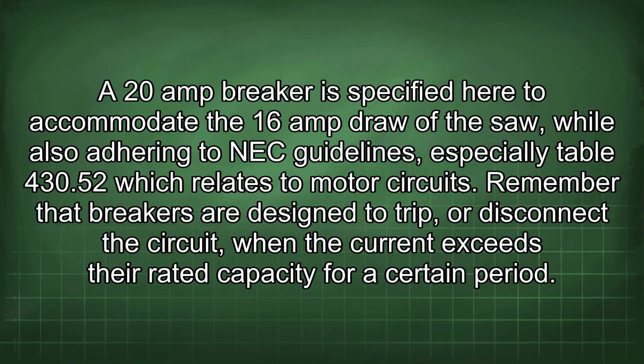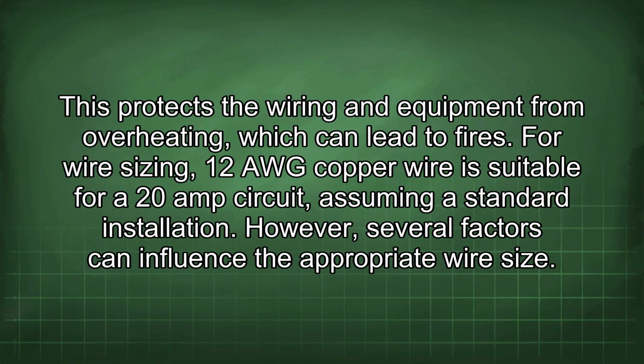Remember that breakers are designed to trip or disconnect the circuit when the current exceeds their rated capacity for a certain period. This protects the wiring and equipment from overheating, which can lead to fires. For wire sizing, 12 AWG copper wire is suitable for a 20 amp circuit, assuming a standard installation. However, several factors can influence the appropriate wire size.